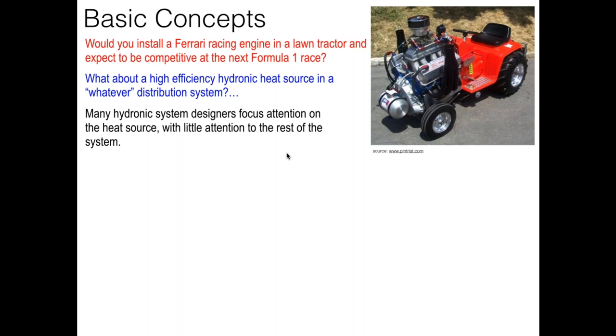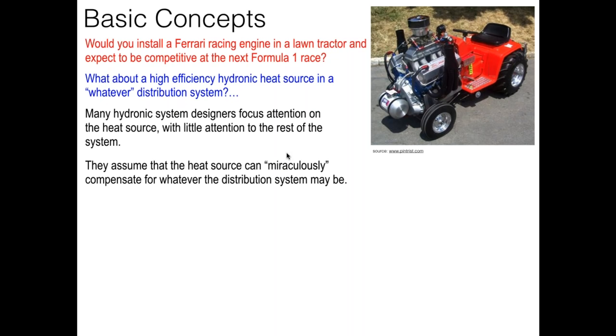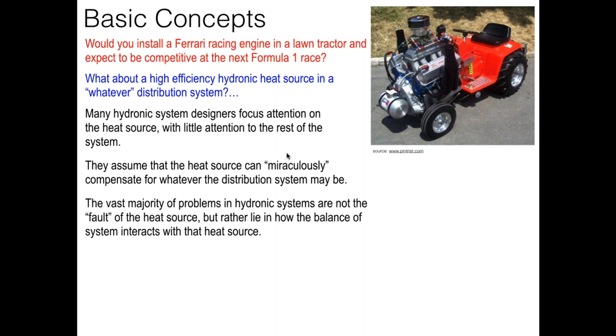We often get myopic, focusing our attention on the heat source. A classic example: you love the performance characteristics of a geothermal heat pump, and you simply assume you're going to connect it the same way you'd connect a cast iron boiler — to the same distribution system — and it's just going to work. We assume miraculous compatibility between that new heat source and the existing distribution system. Of course, problems develop. Experience shows that in many problematic jobs, it's not the fault of the heat source; it's that it simply can't operate in concert with the distribution system connected to it.